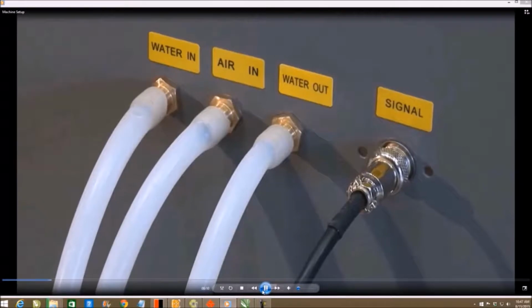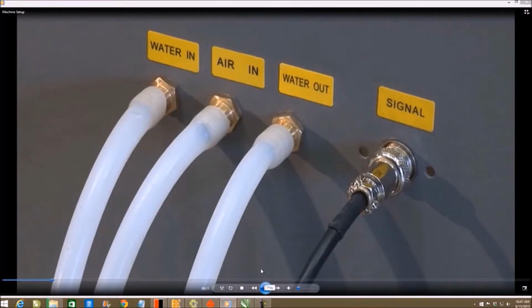and point out something to you that I believe is important. Water in comes from water out of the chiller. Water out goes to water in of the chiller. Air in only goes to the pump. We've had people plug the water into the air by accident. Make sure you don't do that. You have a signal cable here that will go to the blower.